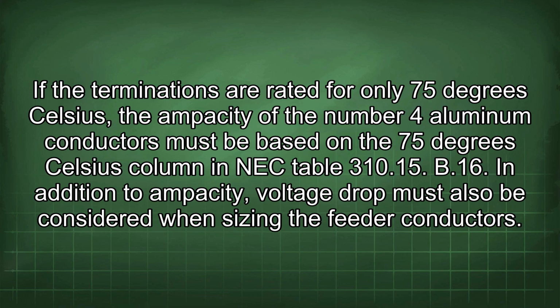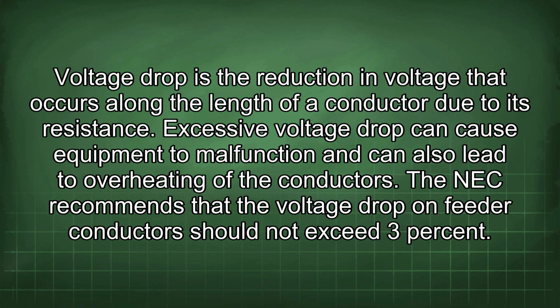In addition to ampacity, voltage drop must also be considered when sizing the feeder conductors. Voltage drop is the reduction in voltage that occurs along the length of a conductor due to its resistance. Excessive voltage drop can cause equipment to malfunction and can also lead to overheating of the conductors. The NEC recommends that the voltage drop on feeder conductors should not exceed 3%.